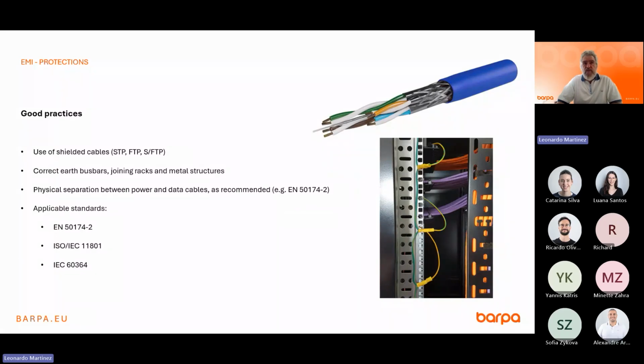Maintain a good physical separation between power and data cable. In the EN 50174-2 standard, there is a beautiful table that explains this physical separation needed between power and data cables, depending on the type of electrical power circuits used, the runways used for installing the cables, the trays, and also the construction of the cable. And of course, a cable with better shielding will prevent interference from power cables.